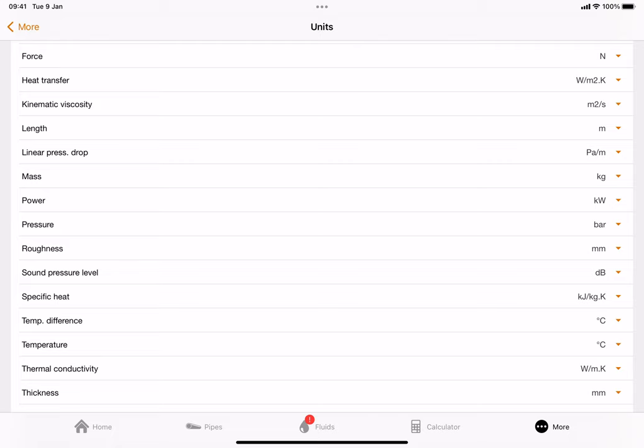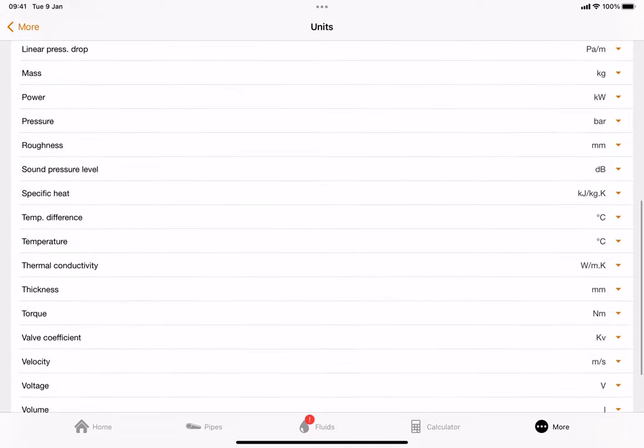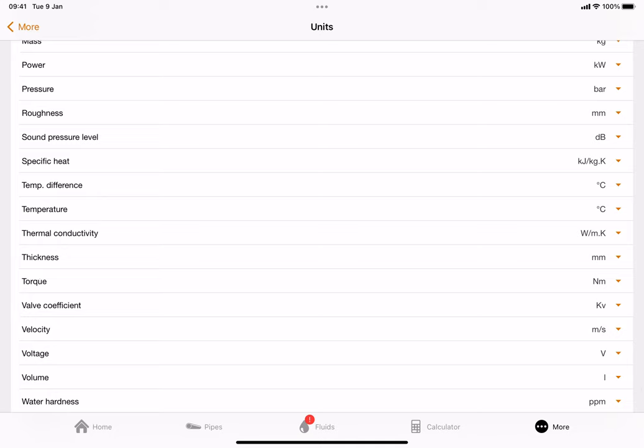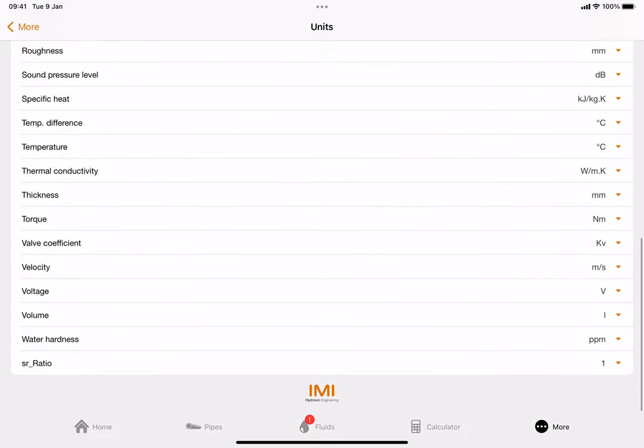Roughness in millimeters - that's also quite important. Sound pressure level in dB. The next one, very important that everybody gets this correct: specific heat - we want it exactly as shown on the screen, which is kilojoules per kilogram Kelvin. Temperature difference and temperature can stay in centigrade. Thermal conductivity in watts per meter Kelvin, thickness in millimeters. The valve coefficient is good to be in KV as that will help you specify valves later. Velocity we want in meters per second, voltage in V, volume in liters, and water hardness in parts per million.